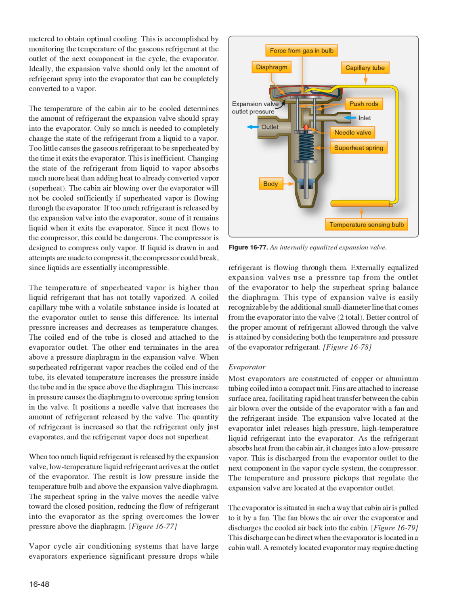This increase in pressure causes the diaphragm to overcome spring tension in the valve. It positions a needle valve that increases the amount of refrigerant released by the valve. The quantity of refrigerant is increased so that the refrigerant only just evaporates, and the refrigerant vapor does not superheat. When too much liquid refrigerant is released by the expansion valve, low-temperature liquid refrigerant arrives at the outlet of the evaporator. The result is low pressure inside the temperature bulb and above the expansion valve diaphragm. The superheat spring in the valve moves the needle valve toward the closed position, reducing the flow of refrigerant into the evaporator as the spring overcomes the lower pressure above the diaphragm.